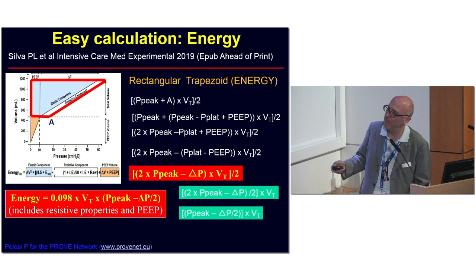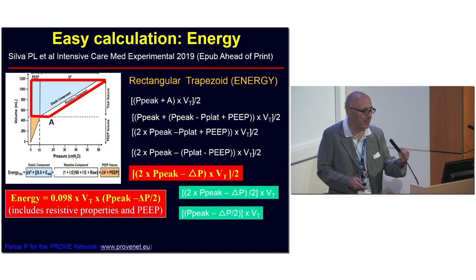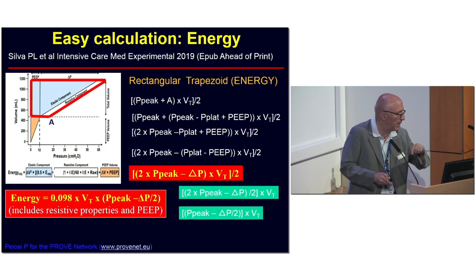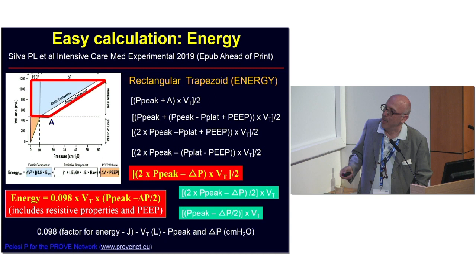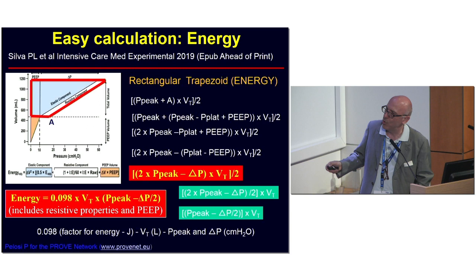So this is the energy: tidal volume, times the peak minus driving pressure divided by 2, times 0.098, which is a constant to convert from centimeters of water and liters to joules, okay? So this is the factor of energy - tidal volume in liters, peak and driving pressure in centimeters of water. This is the energy delivered to the lung for each breath in controlled mechanical ventilation, in volume control.